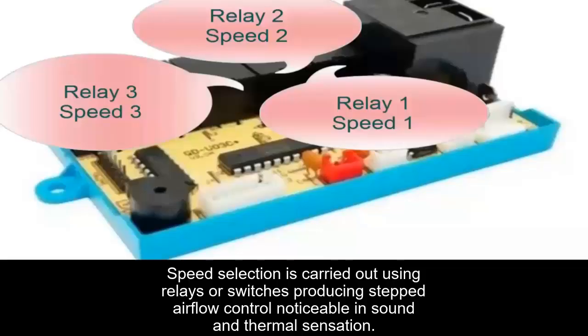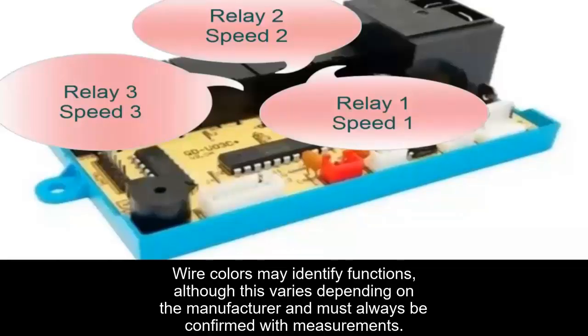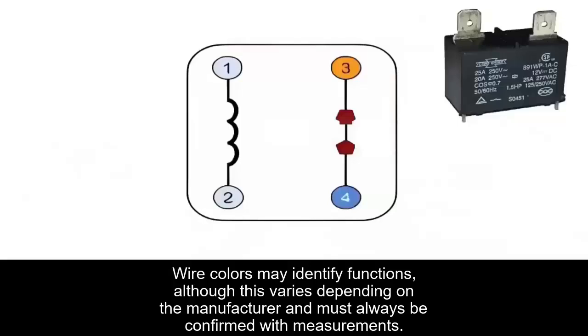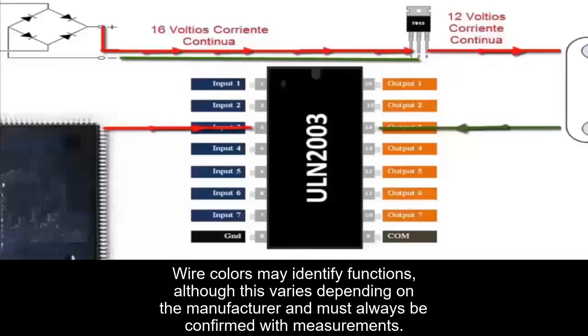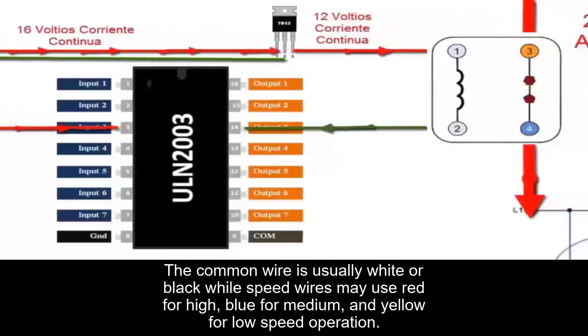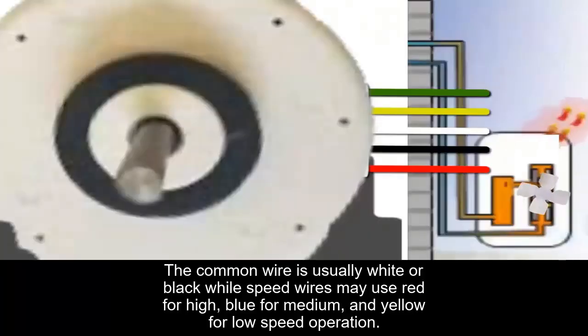and thermal sensation. In many units, wire colors help identify their function, although this may vary depending on the manufacturer. Commonly, the common wire is usually white or black, while the speed wires may be identified as red for high, blue for medium, and yellow for low, although it is always necessary to confirm this with measurements.